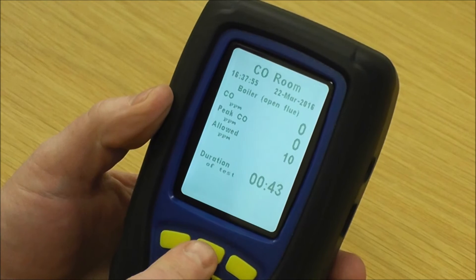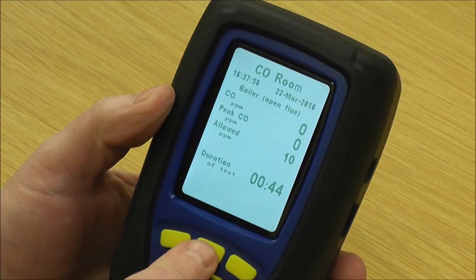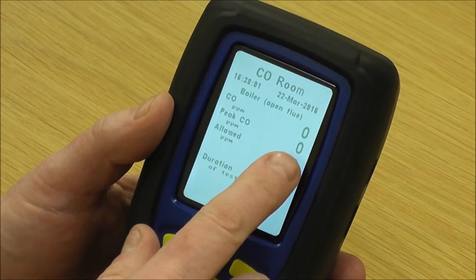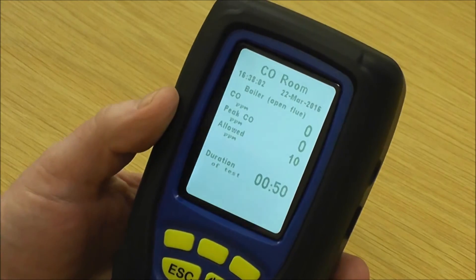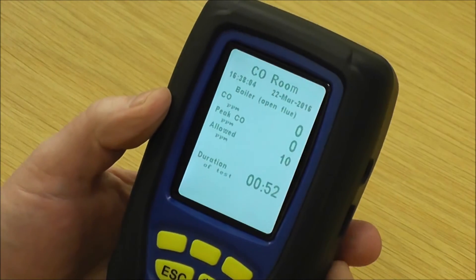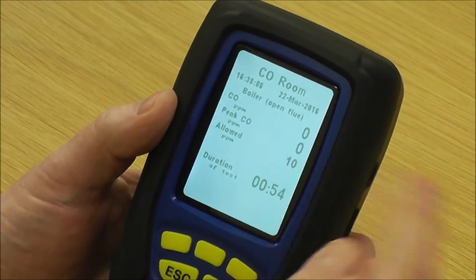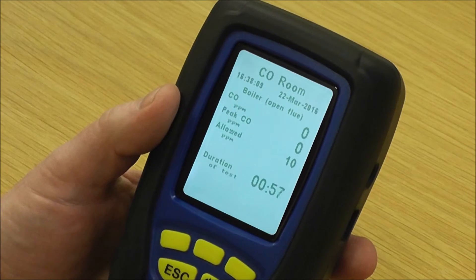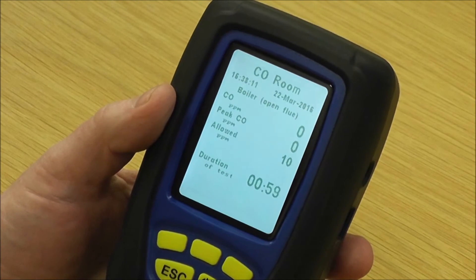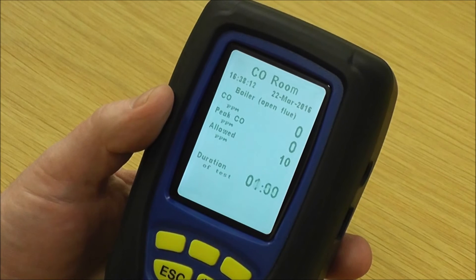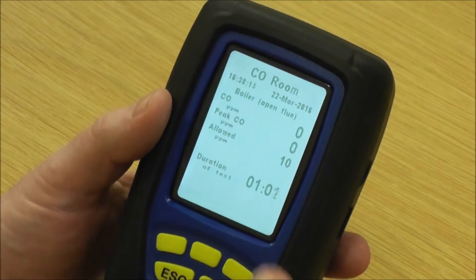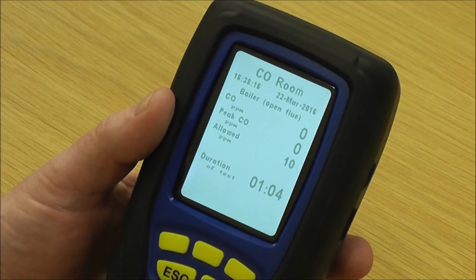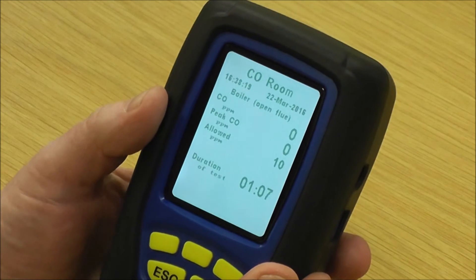Your CO is obviously zero. If the peak CO was at 9 ppm, you'd be concerned knowing that your allowance is 10, so that's when you'd let it run on for the second period. If it was at 2 ppm and your peak CO is 2, as soon as you were allowed to stop it, you'd stop the test and the analyser would pass it for you.